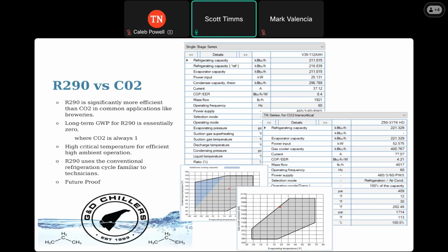So this is kind of just giving some numbers on the efficiency. So you can see on the right here, we have some sizing software output. That COP over EER, that's essentially the efficiency, BTU per hour, so the cooling capacity per watt of power that you have to put into the compressor. So you want that number to be high. So with propane, we're at 8.4, whereas with CO2, we're at 4.2. So it takes twice as much power to get the same amount of cooling with a CO2 system as it does with a propane system, is essentially what that's saying. So the other side of that is that, like I said earlier, the long-term GWP is essentially zero, so that helps. Yeah, all right, I've kind of touched on all those, so we can move to the next one.